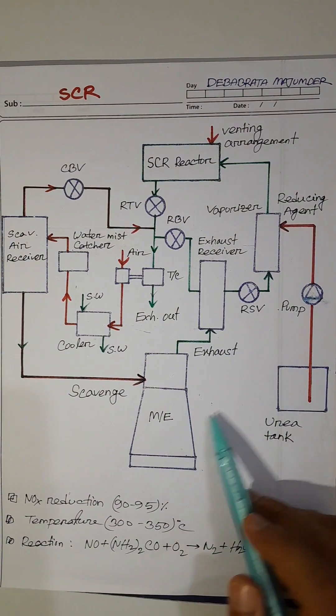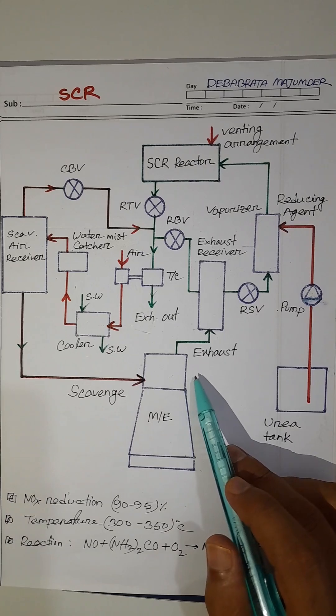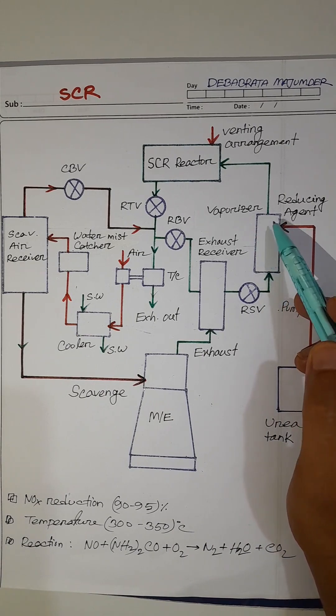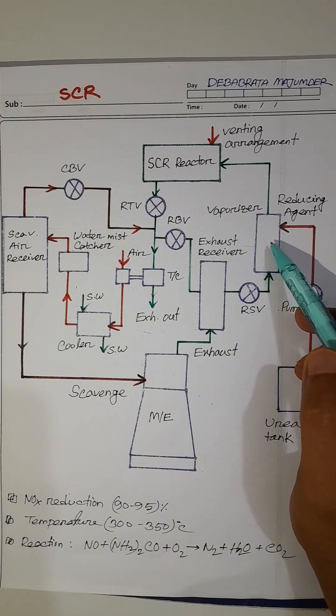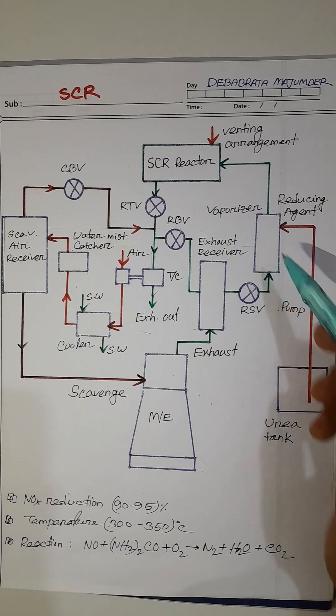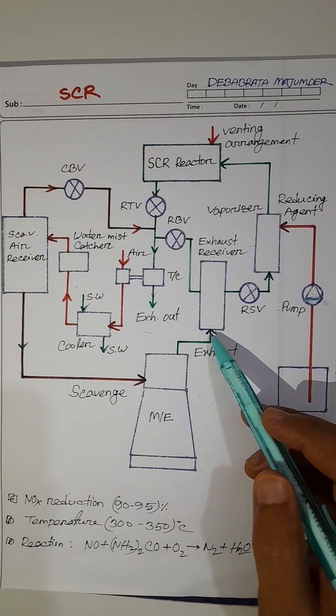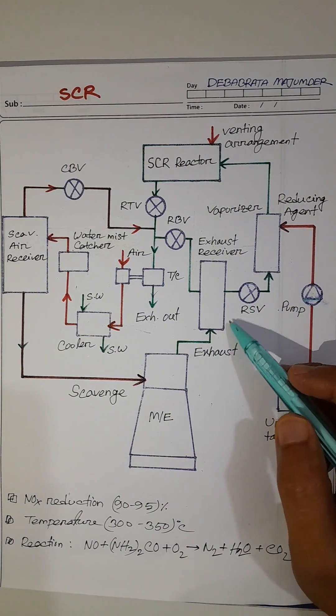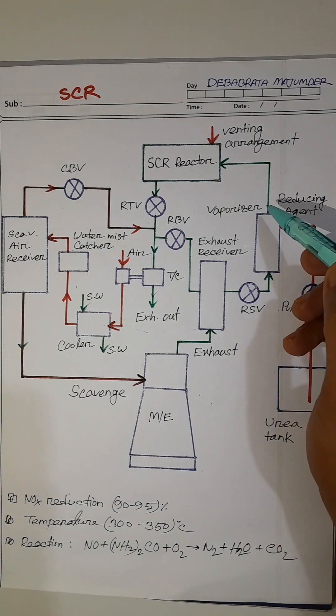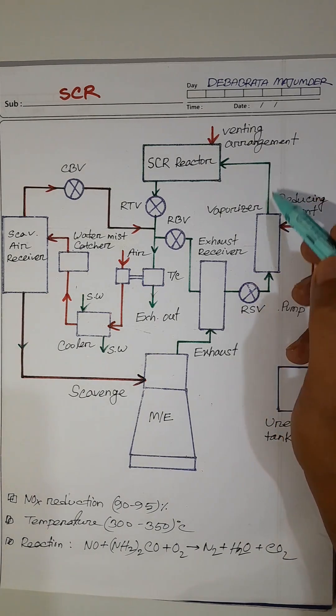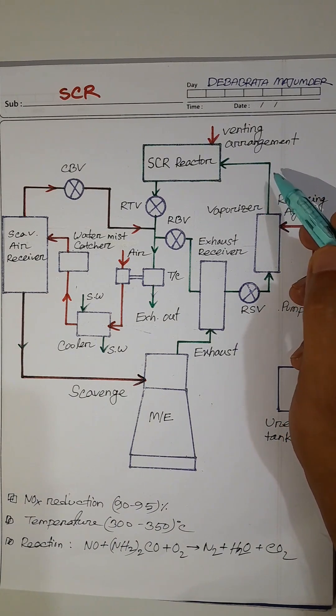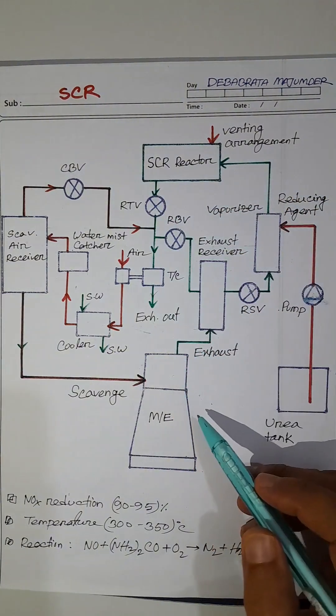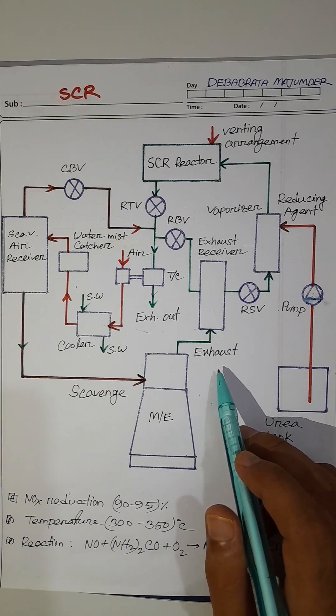Whenever the exhaust gas temperature is above 500 degrees centigrade, the urea is burned and unable to absorb NOx — high temperature is undesirable. Also, at low exhaust gas temperature, urea cannot decompose into ammonia and is unable to absorb NOx, and the urea will deposit and block the exhaust gas piping. So both low temperature and high temperature are undesirable.